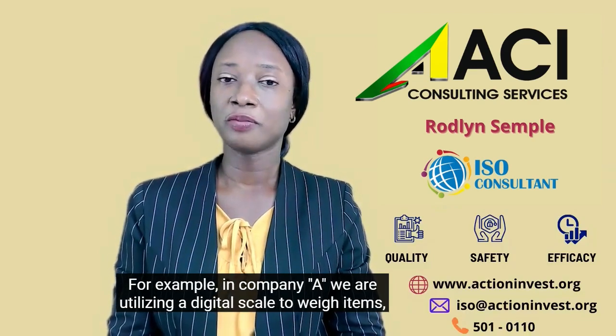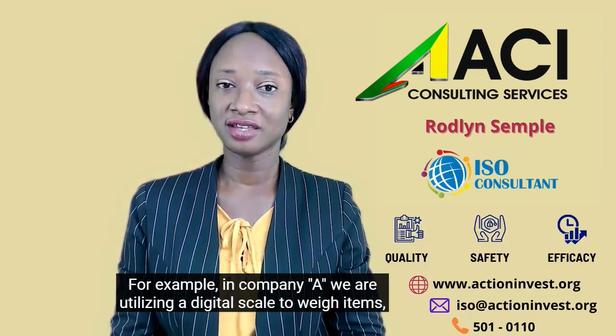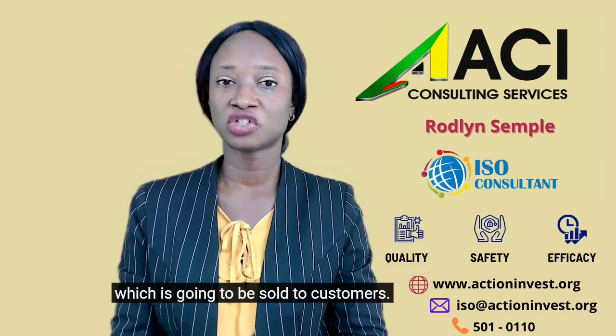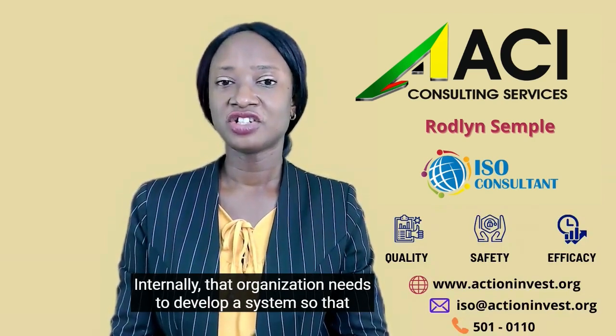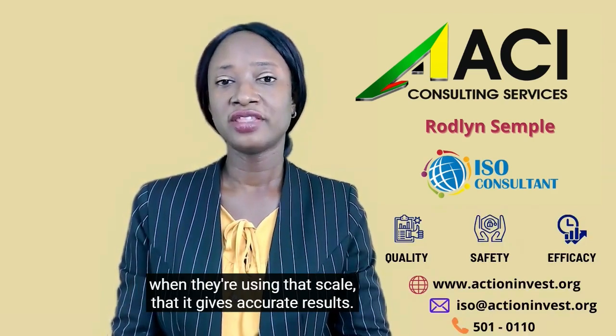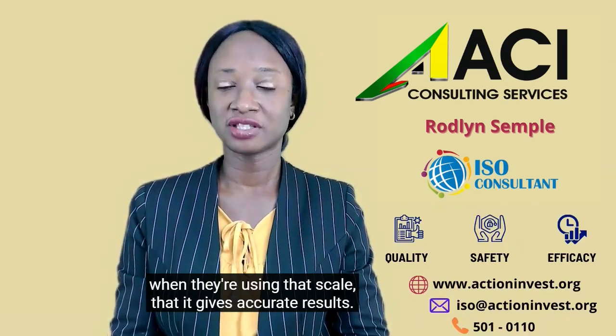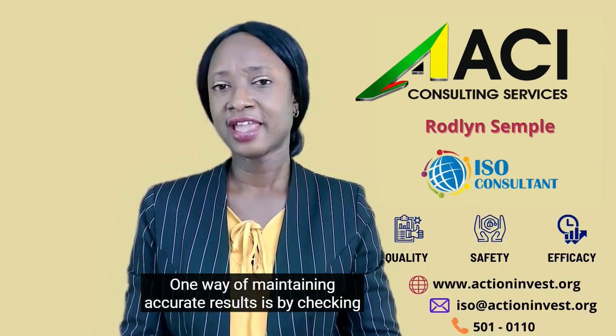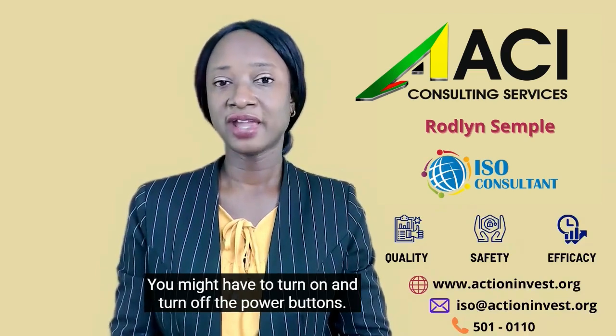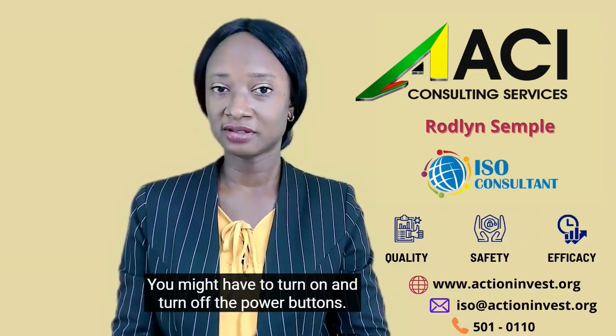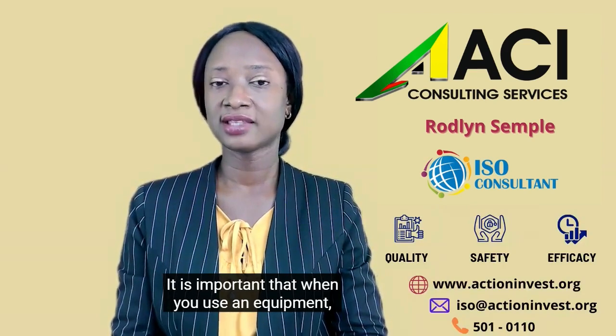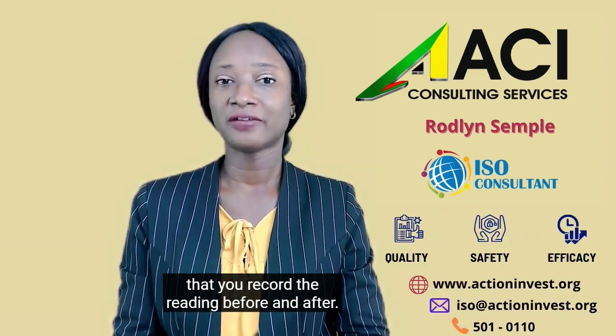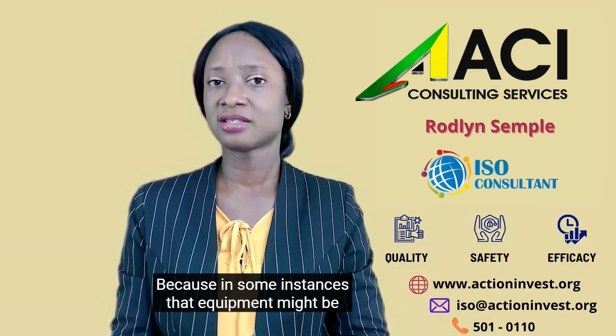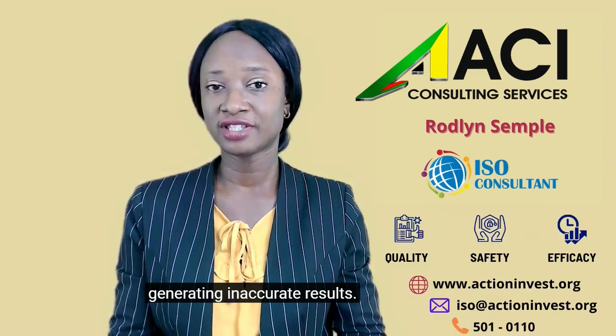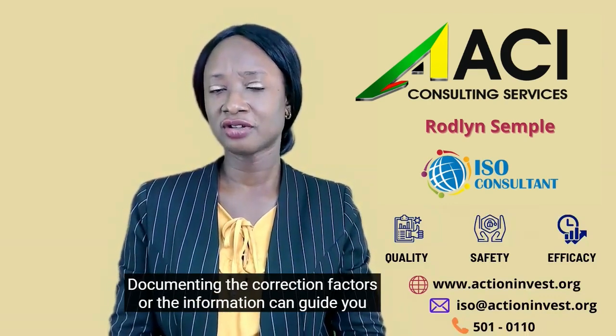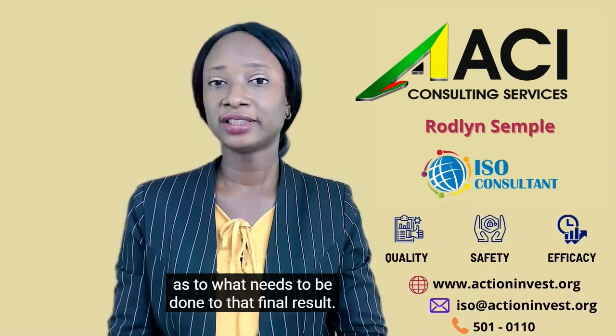For example, in company A, we are utilizing a digital scale to weigh items which are going to be sold to customers. Internally, that organization needs to develop a system so that when they are using that scale, it gives accurate results. One way of maintaining accurate results is by checking before the equipment is used. You might have to turn the power buttons on and off. It is important that when you use equipment, you record the reading before and after. Why? Because in some instances, that equipment might be generating inaccurate results. Documenting the correction factors or the information can guide you as to what needs to be done to that final result.